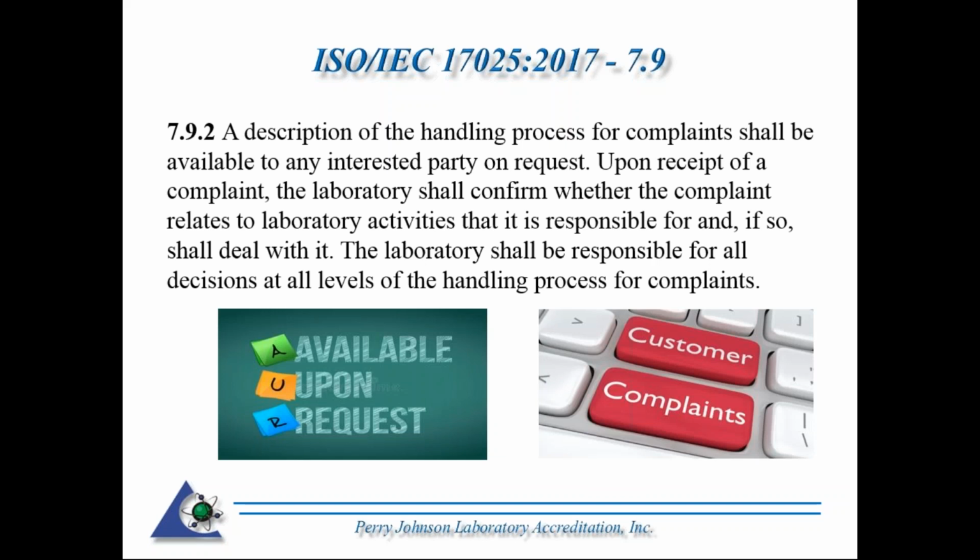Okay, so we have a process in place. 7.9.2, a description of the handling process for complaints shall be made available to any interested party on request. Upon receipt of a complaint, the laboratory shall confirm whether the complaint relates to laboratory activities that it is responsible for, and if so, and I like this part, shall deal with it. The laboratory shall be responsible for all decisions at all levels of the handling process for complaints.